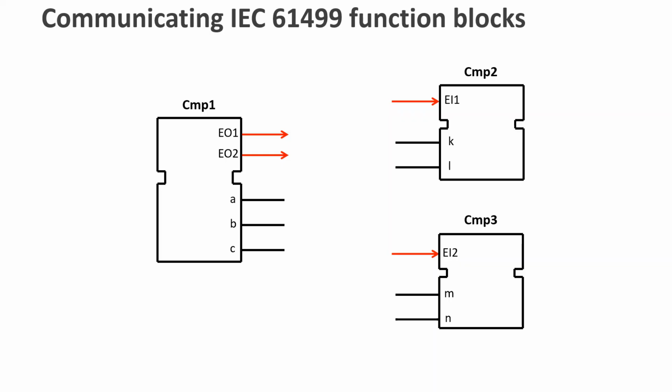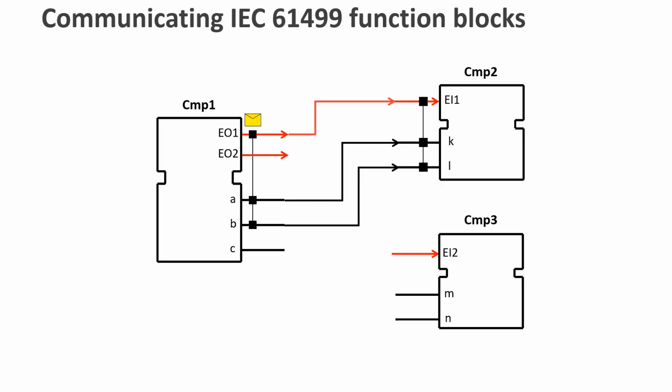Okay, now let us see how our dream about peer-to-peer communicating software components is implemented by the mechanisms of IEC 61499. In IEC 61499, each datagram that is sent by a function block to another function block is implemented by means of an event output and its associated data outputs. When we connect this function block with a corresponding recipient block by event and data connection lines, and the recipient function block has exactly the same matching event and data association, then we can send the datagram and it will arrive at the destination block.